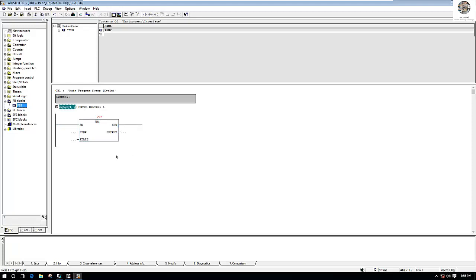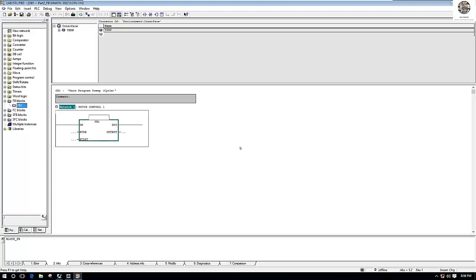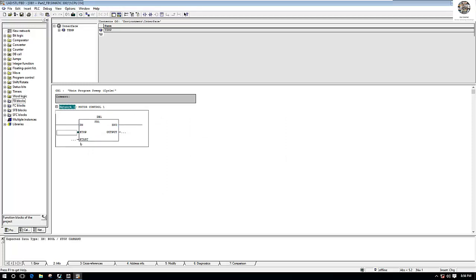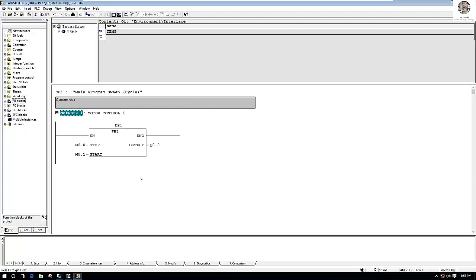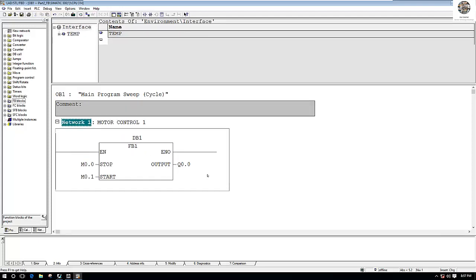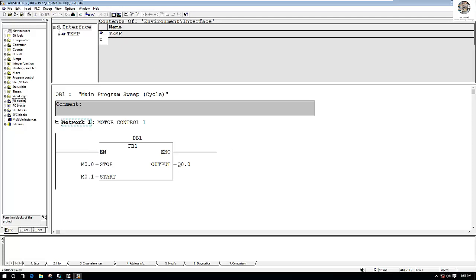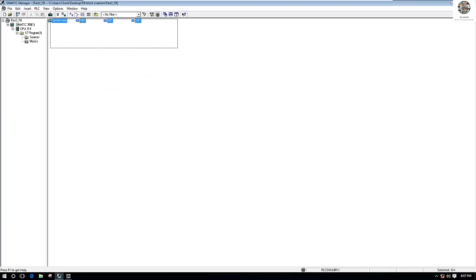We will solve the two inputs and one output. We will assign a data block — for example DB1. Then assign the addresses: for input, example M0.0 and M0.1; for the output, start from Q0.0. So this is the function block that we already created. Save the project and then download all blocks to the CPU again, because we just added and modified the block. Select all blocks and then click Download, choose All.